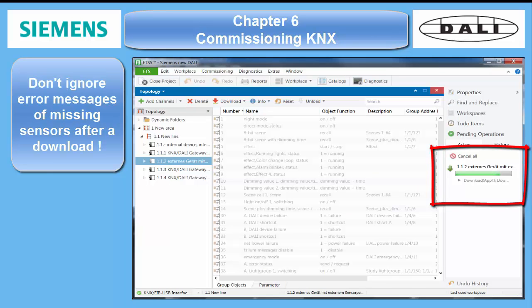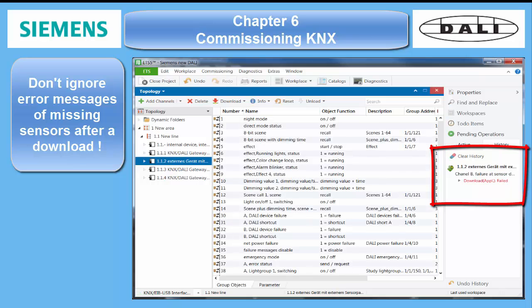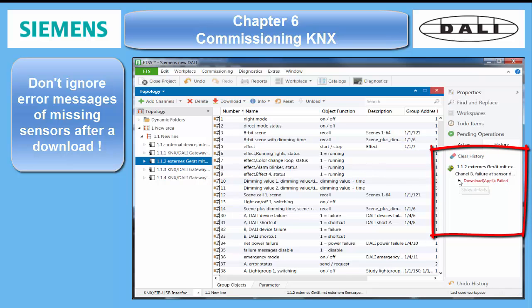Other error messages which can occur often refer to the sensors. The absence of a previously installed sensor is recognized each time a download is committed. Other than with missing ECG, a missing sensor will lead to a warning message in the history of bus access in ETS. So don't ignore such a message, but try to solve the problem and check the assignment of the sensors once more in the live commissioning tool of the DALI gateway.